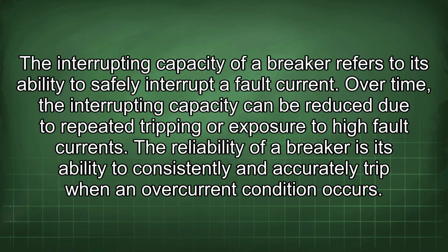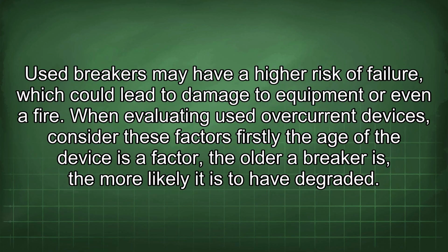The interrupting capacity of a breaker refers to its ability to safely interrupt a fault current. Over time, the interrupting capacity can be reduced due to repeated tripping or exposure to high fault currents. The reliability of a breaker is its ability to consistently and accurately trip when an overcurrent condition occurs. Used breakers may have a higher risk of failure, which could lead to damage to equipment or even a fire. When evaluating used overcurrent devices, consider these factors.